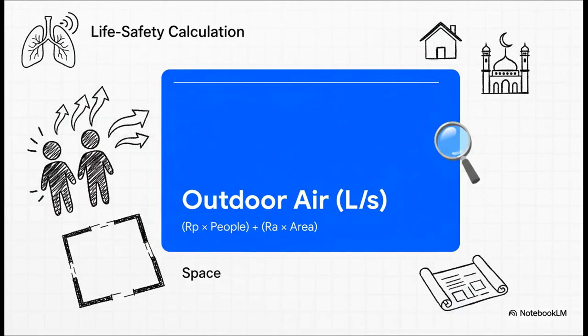The right way to do it is actually pretty simple. It has nothing to do with cooling load. It's all about people and space. You just take the airflow rate required per person, add the rate required for the area, and that's your number. See, it's a life safety formula, not a comfort formula.